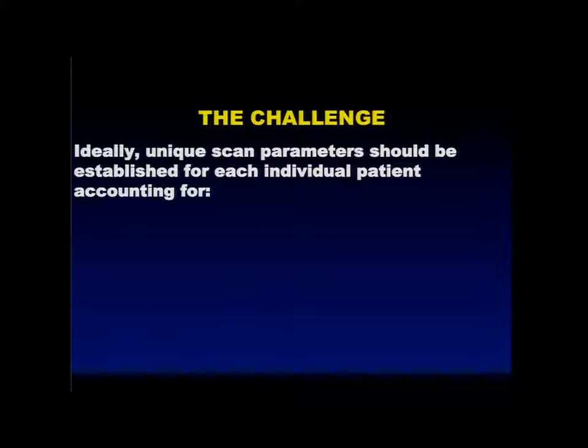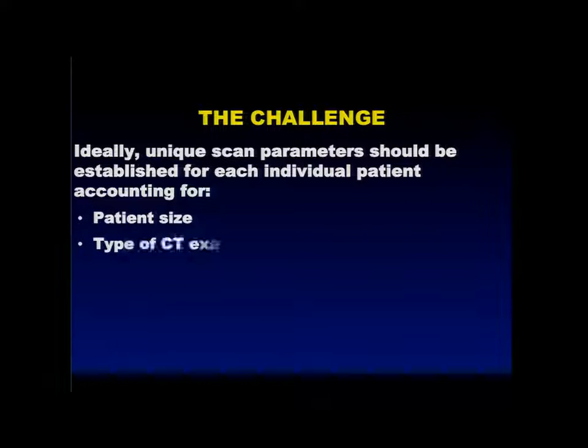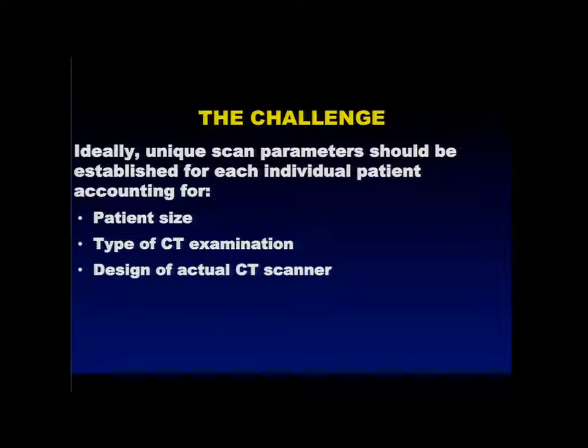Our challenge is that ideally unique scan parameters should be established for each individual patient, accounting for their size, the type of CT examination, and the unique design characteristics of the CT scanner. If I've got eight different CT scanners in my department, I need a detailed technique chart for each one. For each exam, I need techniques for six different size patients. All of a sudden you're talking about a thousand different combinations of technique charts.